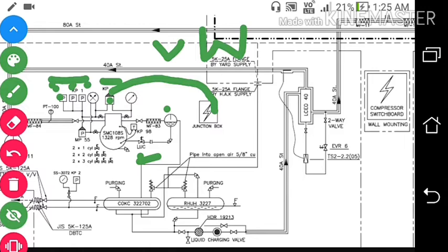So you can see, during light load only 2 cylinders will be in operation, and during more than that 4 cylinders will be in operation, and more than that 6 cylinders will be in operation. So depending upon the pressure at the inlet to the compressor, the unloading valve operates. Unloading of cylinders takes place during starting and for subsequent load control by holding the suction valve off their seats by a suitable oil pressure operated mechanism. I will tell you later on how this unloader works.